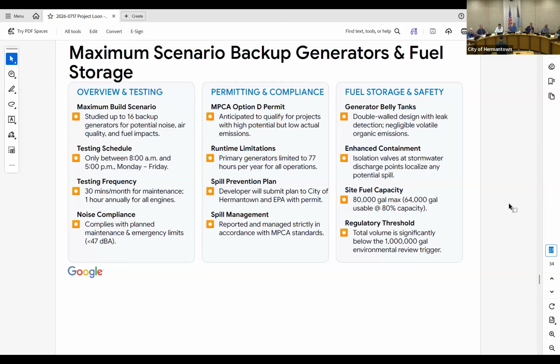The site fuel capacity is similar to the backup generators. In the AUAR, we studied up to just shy of 100,000 gallons of on-site renewable diesel stored on-site, but with the reduction of data center buildings on the campus to 3, and a corresponding reduction in assumed backup generators, the fuel capacity would be reduced to at most 80,000 gallons if the belly tanks were fully filled. Typically for operations those would be capped at an 80% level. The regulatory threshold for any additional environmental review related to diesel storage is 1 million gallons on site, which we are far less than.